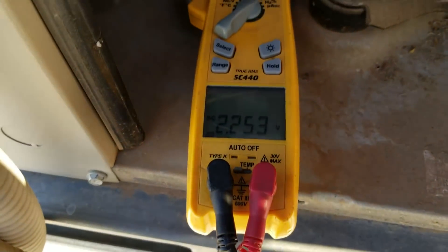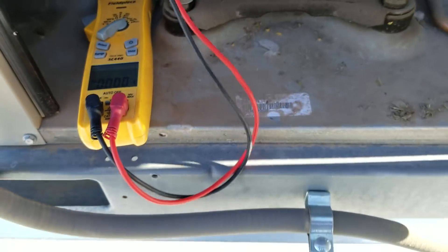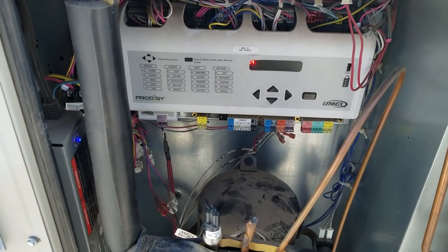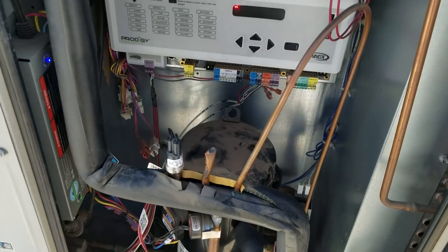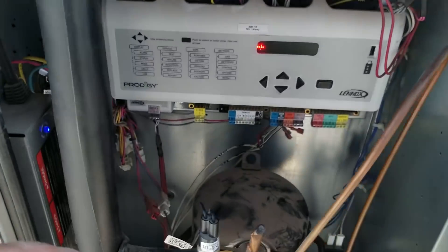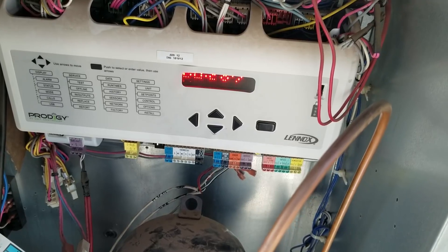Scared the crap out of me. My CO2 is now reading what the actual CO2 meter is showing down there — 2.2 volts DC — and I'm reading that high voltage over on the humidity input at 3.6 volts, and it's actually dropping down already. When this unit reaches set point, it's going to look at the humidity input versus the humidity set point, and if it's above set point — which it is right now — it's not going to shut off the compressor. It's going to keep running by turning on the reheat, which is opening hot gas through that hot gas coil after the evaporator, to add a little load and keep refrigeration going. Humidity is still way up there, but it's going to continue to run and bring that down.